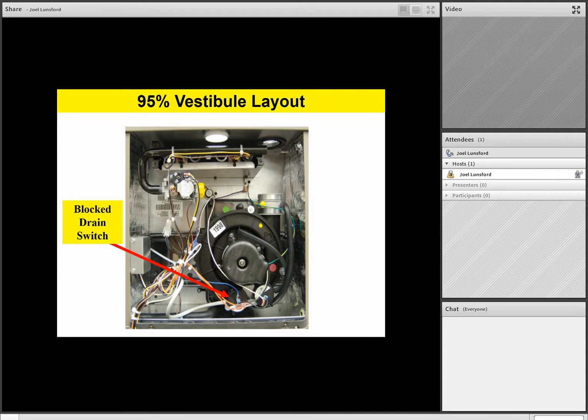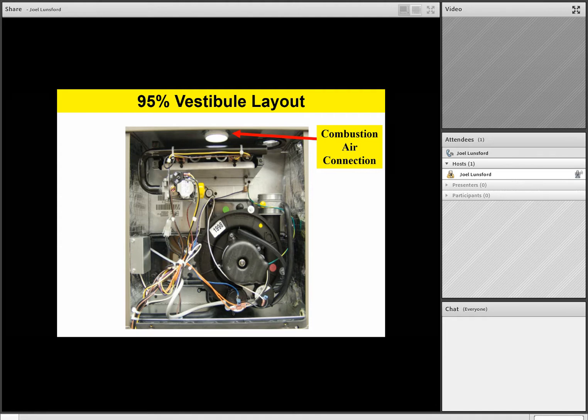There's our block drain switch towards the bottom of the vestibule assembly. And right next to it or near it is going to be our combustion air pressure switch, our safety switch to prove venting. There's our combustion air inlet. And it should be noted that all of our furnaces, including our 95% plus furnaces, are all 4-way convertible. So you have combustion air at the top, or you can have combustion air coming in either side of the vestibule assembly. There's our rollout switch or switches. Based on the size of the furnace, you may have more than one rollout switch.